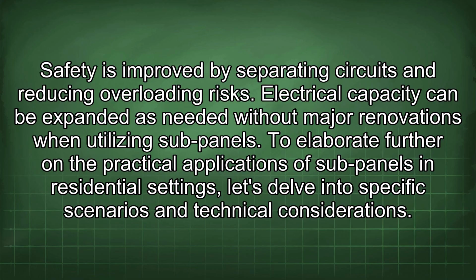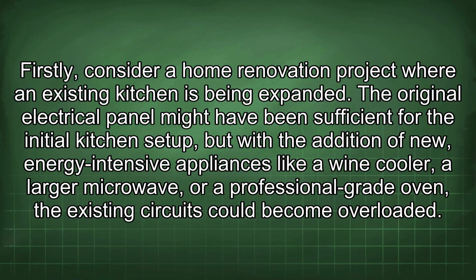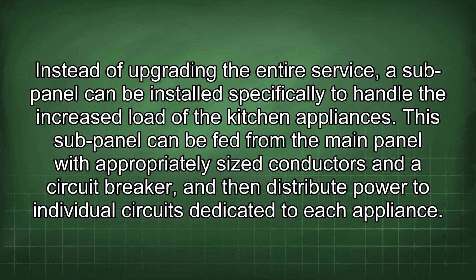To elaborate further on the practical applications of sub-panels in residential settings, let's delve into specific scenarios and technical considerations. Firstly, consider a home renovation project where an existing kitchen is being expanded. The original electrical panel might have been sufficient for the initial kitchen setup, but with the addition of new, energy-intensive appliances like a wine cooler, a larger microwave, or a professional-grade oven, the existing circuits could become overloaded. Instead of upgrading the entire service, a sub-panel can be installed specifically to handle the increased load of the kitchen appliances. This sub-panel can be fed from the main panel with appropriately sized conductors and a circuit breaker, and then distribute power to individual circuits dedicated to each appliance.